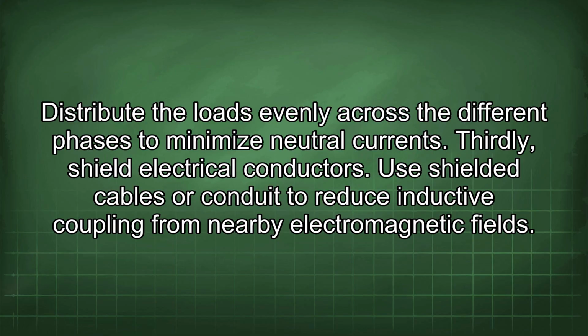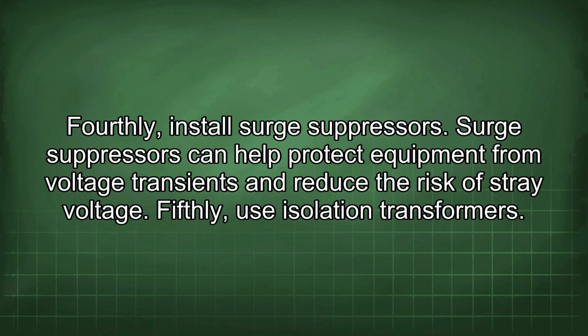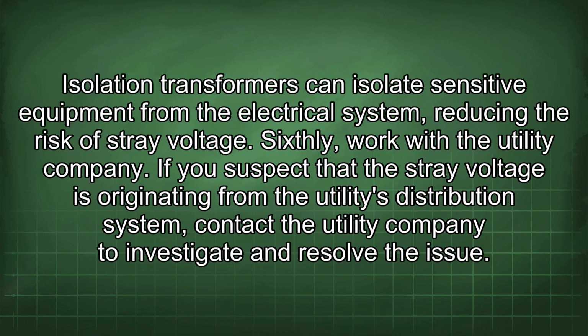Thirdly, shield electrical conductors. Use shielded cables or conduit to reduce inductive coupling from nearby electromagnetic fields. Fourthly, install surge suppressors. Surge suppressors can help protect equipment from voltage transients and reduce the risk of stray voltage. Fifthly, use isolation transformers. Isolation transformers can isolate sensitive equipment from the electrical system, reducing the risk of stray voltage.